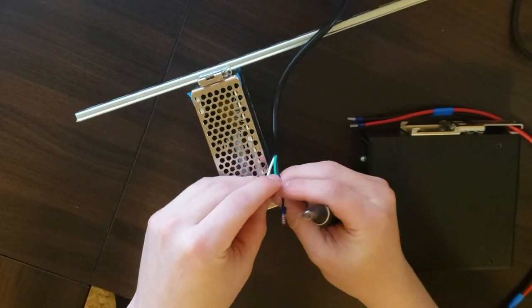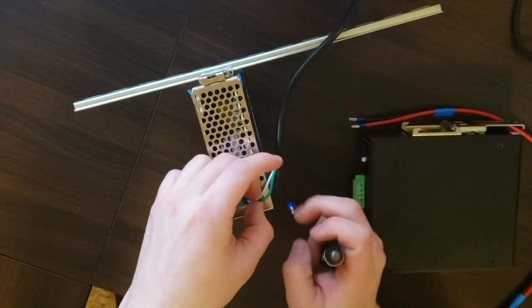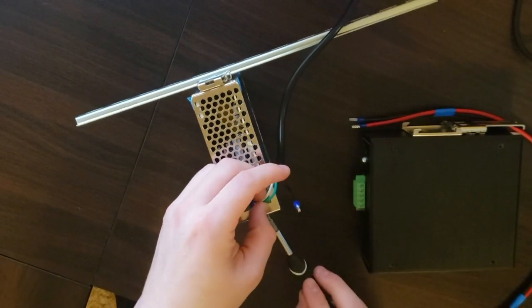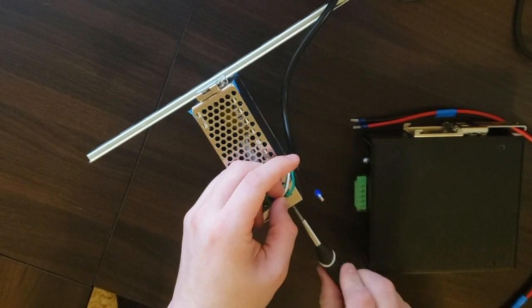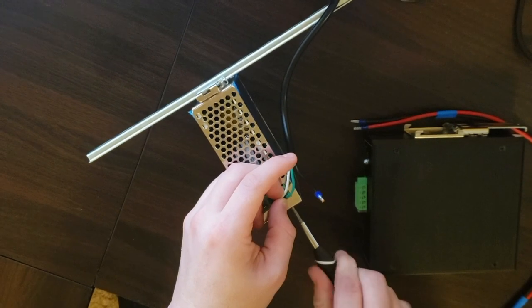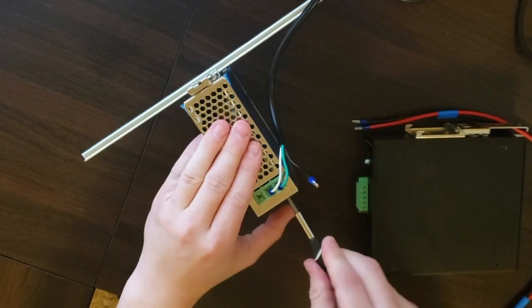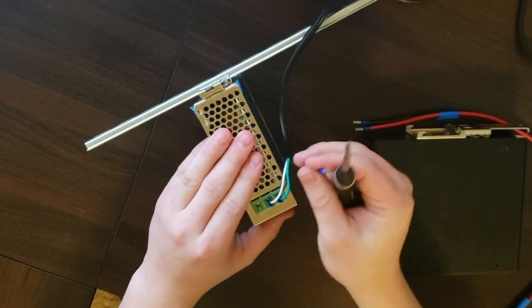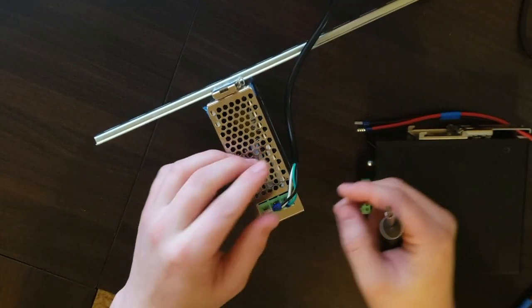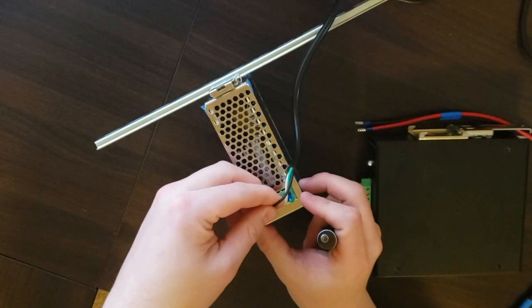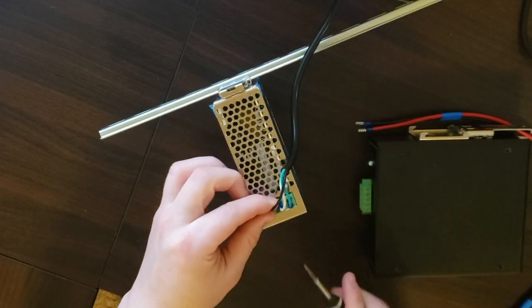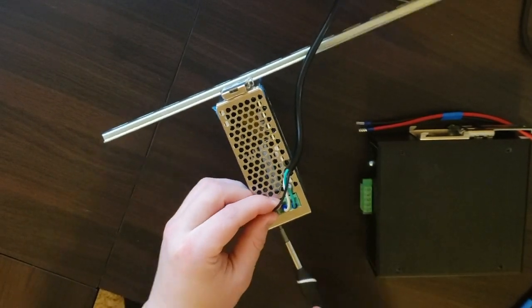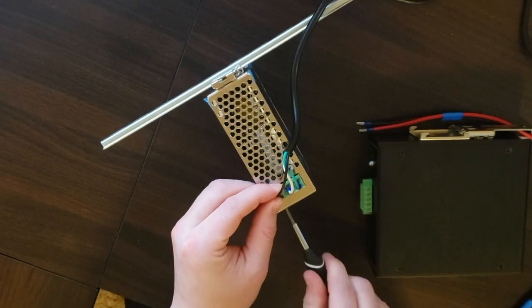Make sure all stranded wires are secured in the terminal block to prevent short circuit. This will keep you and your equipment safe. Input cables must be properly fused. A manually controlled disconnect switch should be used to disconnect the unit from the AC supply mains. All output wires must be rated for 18 gauge or larger as well as connected to the correct polarity.